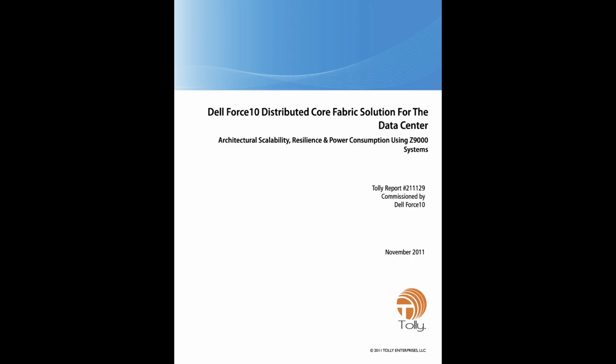Power consumption is a key element of recurring expense for any data center, and can be a significant element of total cost of ownership for switching infrastructure. The power consumption of switches will vary depending upon the workload, i.e. traffic on the switch at any given time. It is important to note that power consumption comparisons must only be made between systems running identical traffic loads.